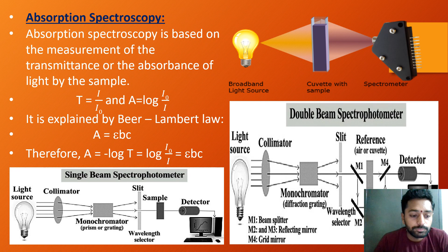Most of the modern spectrophotometers are based on the double beam spectrophotometer design. In a double beam spectrophotometer instrument, two beams are formed by a beam splitter. One beam passes through the sample path and the other passes through the reference path. One beam passes through the reference solution to a photodetector and the second simultaneously traverses the sample to the second or matched detector. The two outputs are amplified and their ratio is determined and displayed by the digital readout device. The double beam design lends itself well to the continuous recording of transmittance or absorption spectra.